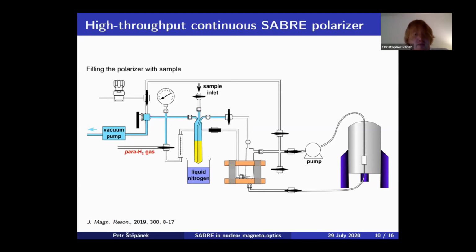What is the volume of liquid being polarized in the polarization vessel in the continuous flow setup? Yes, in this particular setup, the volume is pretty significant, as you can probably imagine. I think that the lowest we achieved was like 40 milliliters, which, given that we can use non-deuterated solvent, is quite achievable. But we were also thinking that this vessel is in principle unnecessarily wide, so it could probably be cut by at least a third by making the vessel more narrow and perhaps higher. And of course, the tubing presents a lot of that volume, so that also contributes to it.